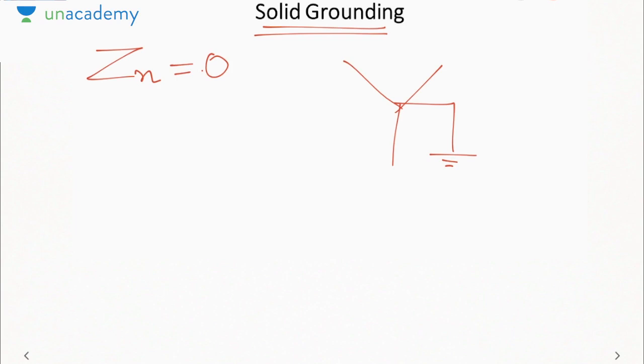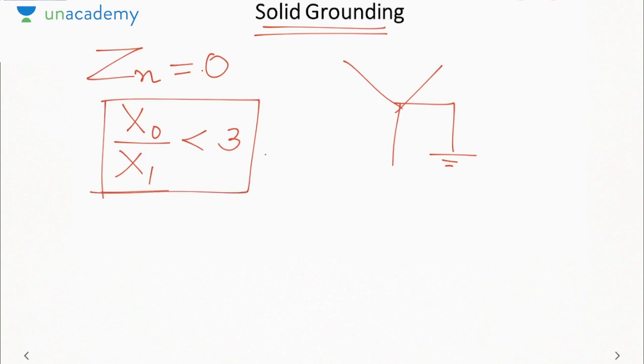First one is called solid grounding. That is, you will directly connect the neutral to the ground. There is no neutral impedance, that is Zn is 0. That is called solid grounding. Now how to decide when you will have to use solid grounding? If zero sequence reactance upon positive sequence reactance of the system is less than 3, we use solid grounding. Okay. So this is the criteria for the case of solid grounding.